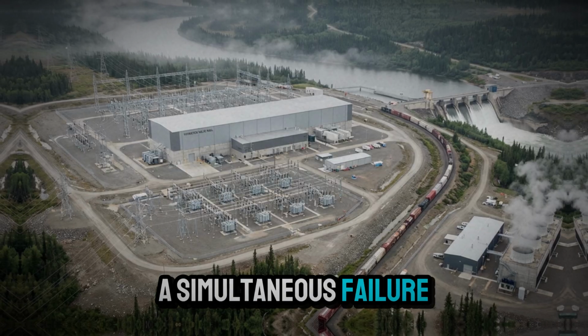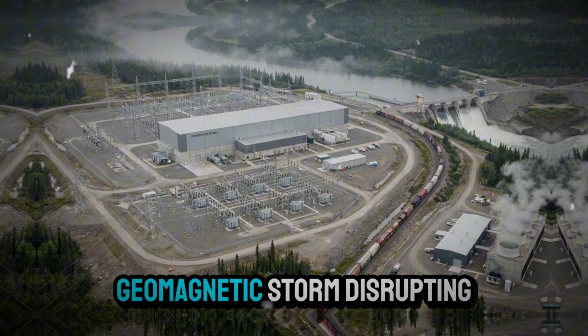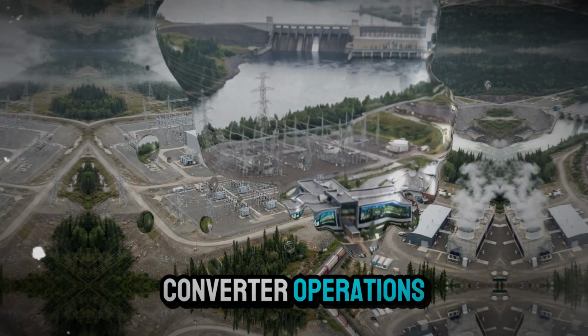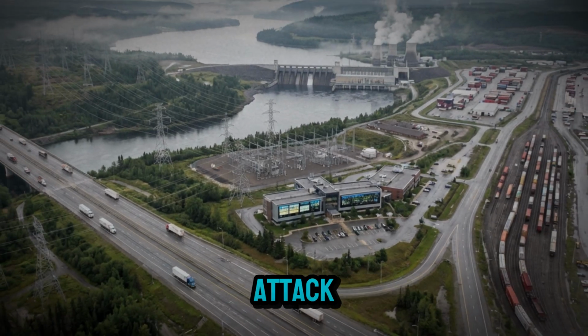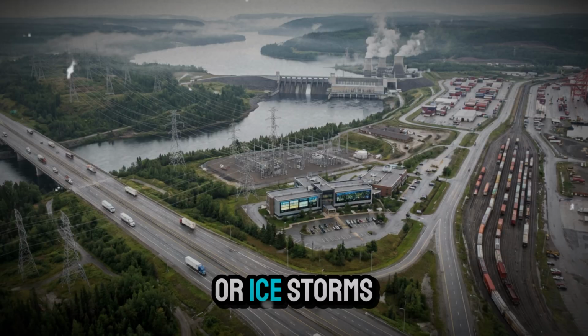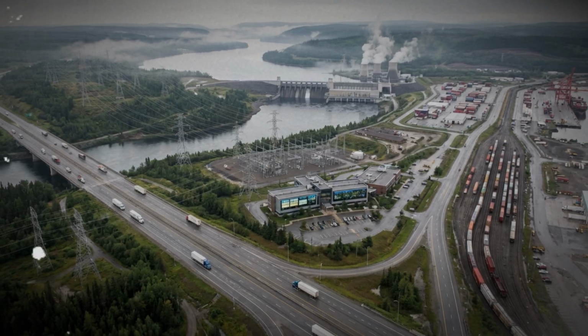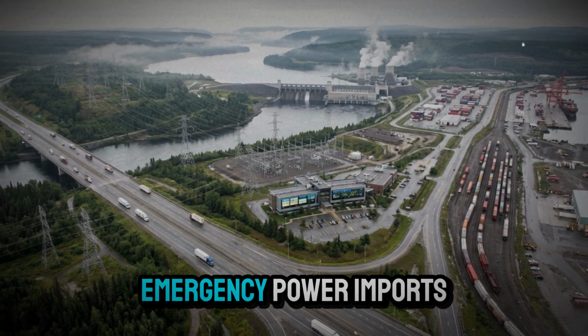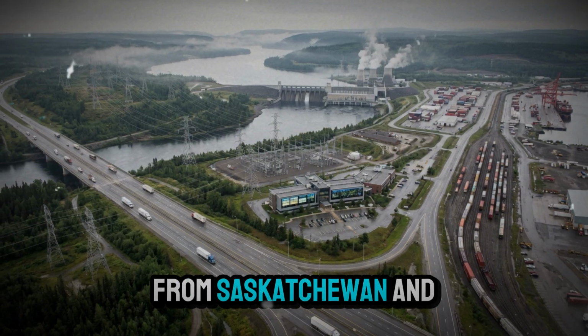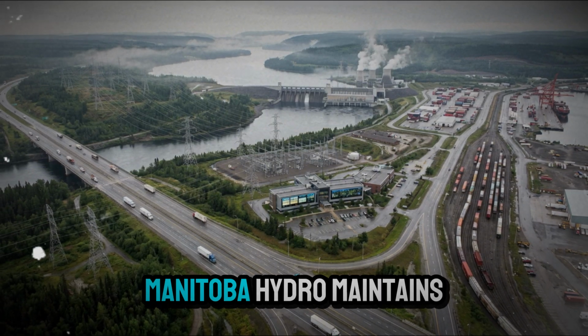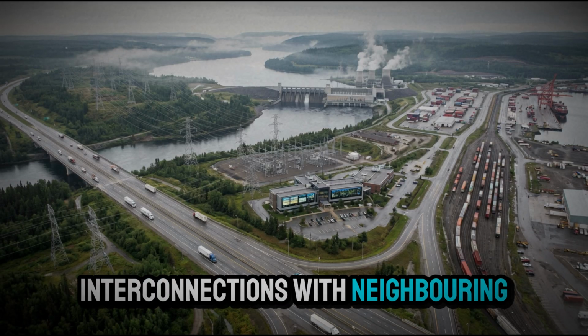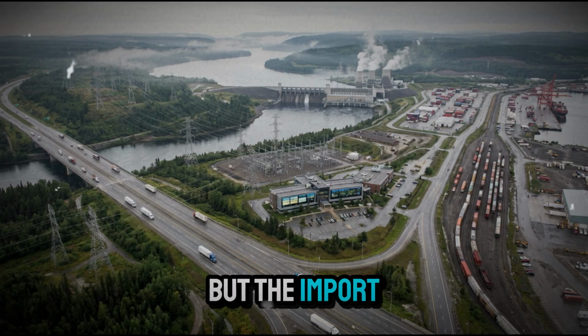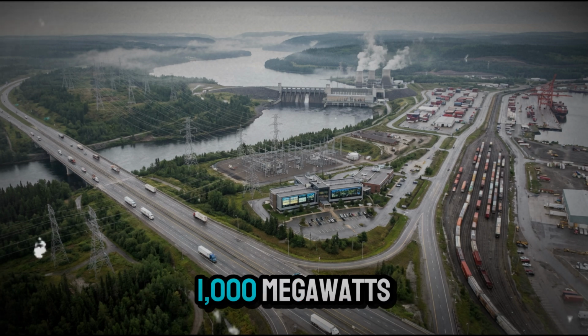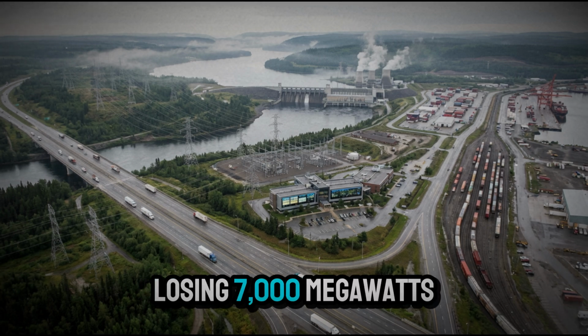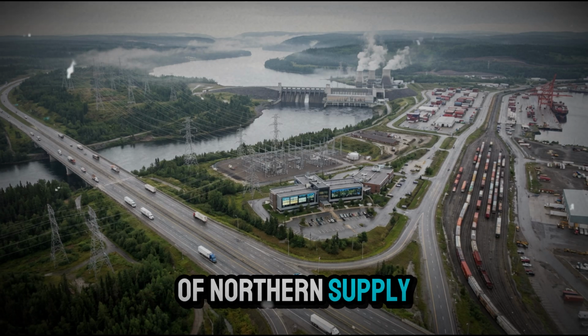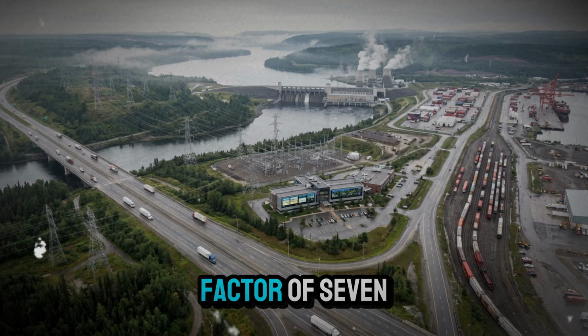A simultaneous failure of the bipoles, whether from a geomagnetic storm disrupting converter operations, a coordinated physical attack on transmission towers, or ice storms bringing down conductors, would immediately require emergency power imports from Saskatchewan and the United States. Manitoba Hydro maintains interconnections with neighboring systems, but the import capacity is approximately 1,000 megawatts.